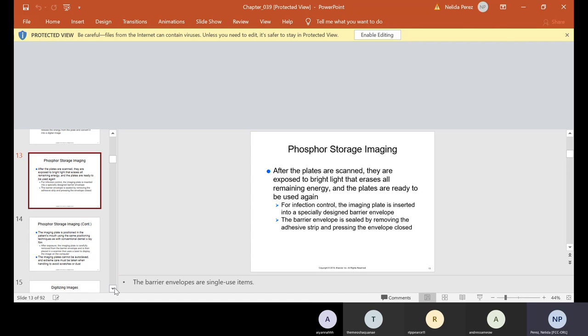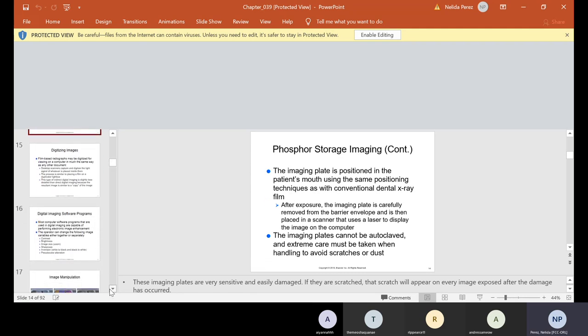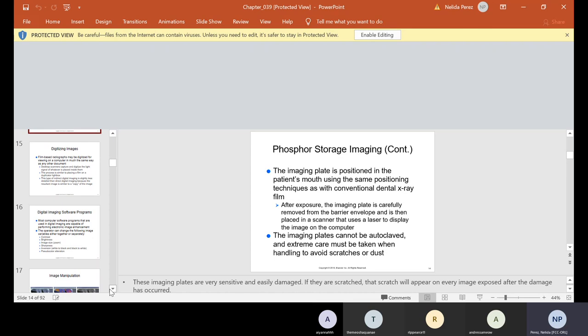After the plates are scanned, they're exposed to bright light that erases all remaining energy, and the plates are ready to be used again. For infection control, the imaging plate is inserted into a specifically designed barrier envelope, sealed by removing the adhesive strip and pressing the envelope closed. The imaging plate is positioned in the patient's mouth using the same positioning techniques as conventional film. After exposure, the plate is carefully removed from the barrier envelope and scanned with a laser to display the image on the computer. The imaging plates cannot be autoclaved and extreme care must be taken to avoid scratches or dust.